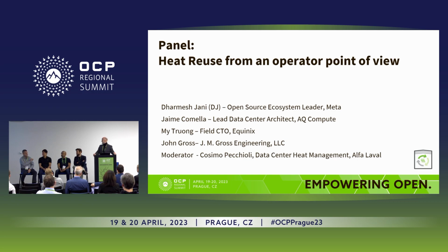If I could add, when we talk about thinking outside the box a little, the traditional concept for heat reuse is heating air, providing process heating for farms, indoor farms, and so on. There are other heat reuse cases that aren't outdoor ambient dependent, like desalinization. The problem is desalinization requires high-grade heat, but that doesn't preclude it from being hooked up to a data center for heat reuse. For anyone developing data centers anywhere in the world and looking at heat reuse cases, I'd ask you to look for any opportunity where there's a process heating load nearby that you can tie into, whether it's ambient dependent or not.